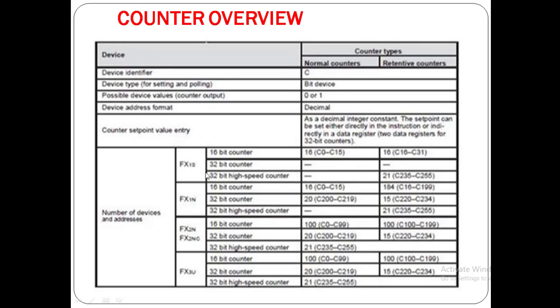In PLC FX1S series, 16-bit counters are 16 from C0 to C15, and 16 are retentive counters which are C16 to C31. 32-bit normal counters are not available in this series. However, 32-bit high-speed counters are available only in retentive type — these are 21, ranging from C235 to C255.